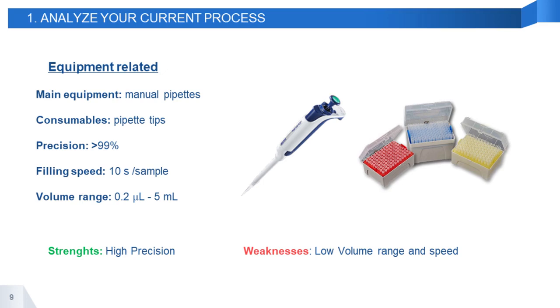We will analyze the filling process with manual pipettes in order to see how it was done and why it needed to be improved. As I said before, the first thing to do is describing the characteristics of your process in order to have a complete understanding of it. In my opinion, the main characteristics of a filling process would be the ones shown here. First, the main equipment used to dispense. In this case, we have manual pipettes that use pipette tips as a consumable. This type of equipment is really precise, over 99% generally, but on the contrary, they are quite slow, with an approximate filling speed of 10 seconds per sample.